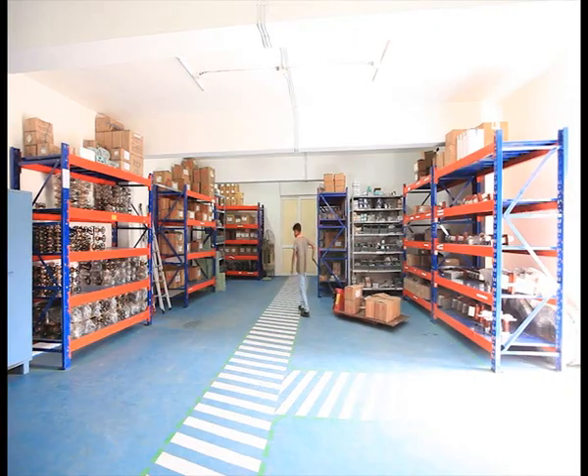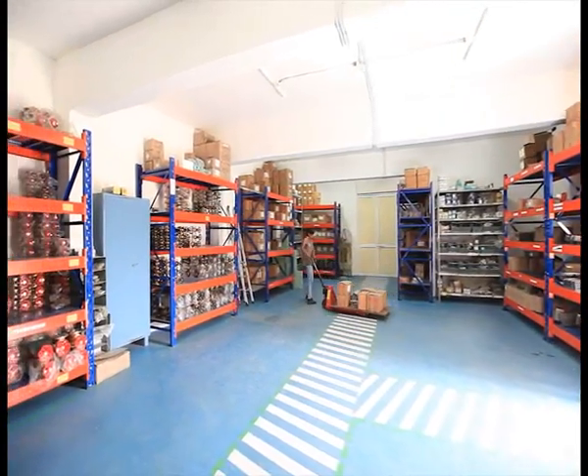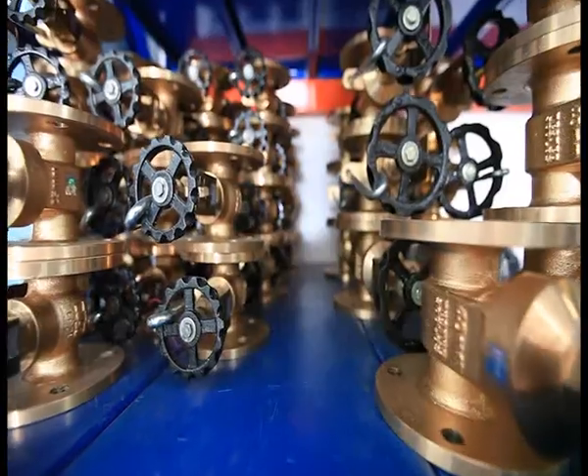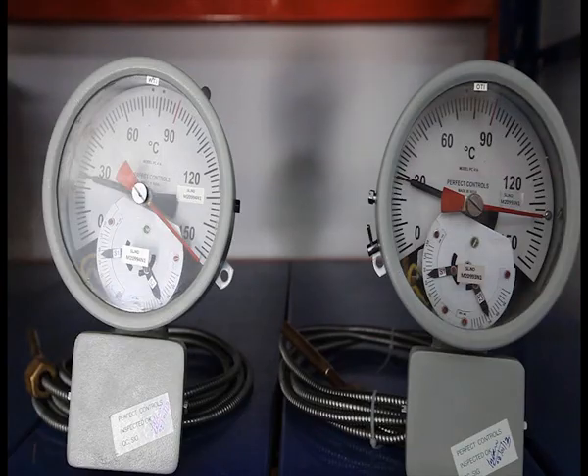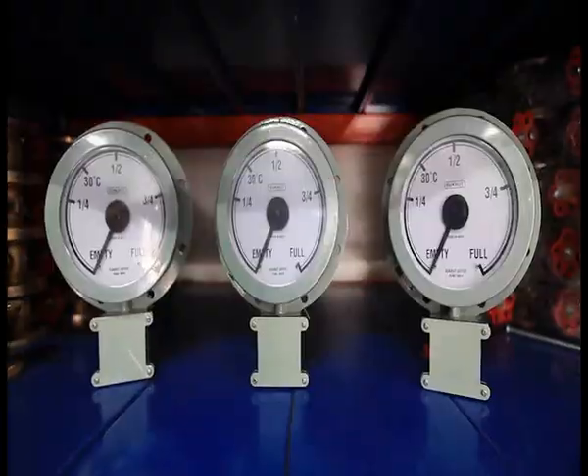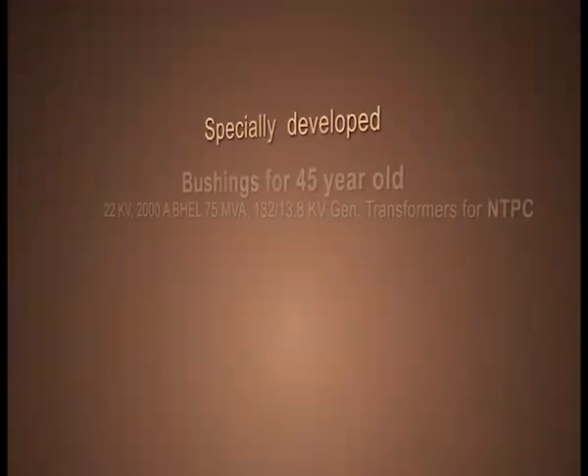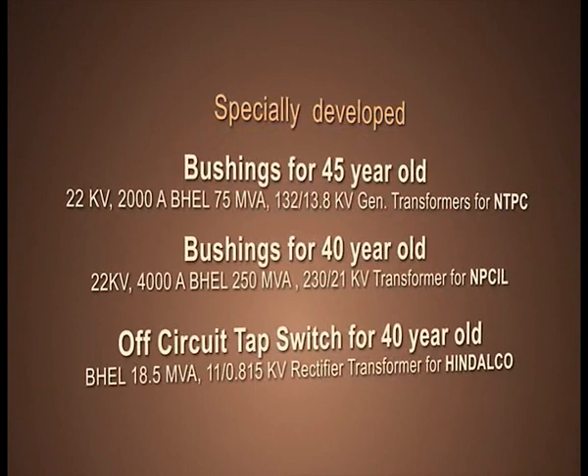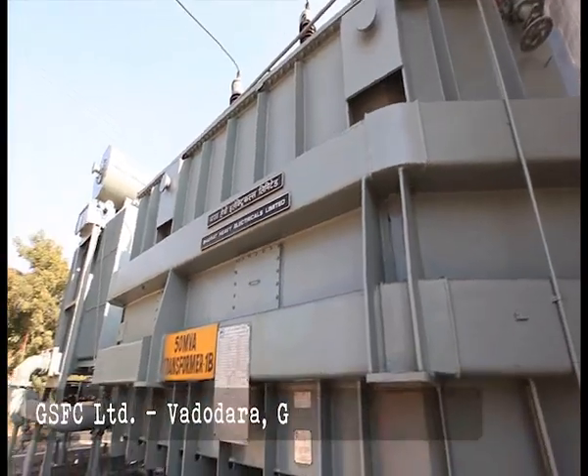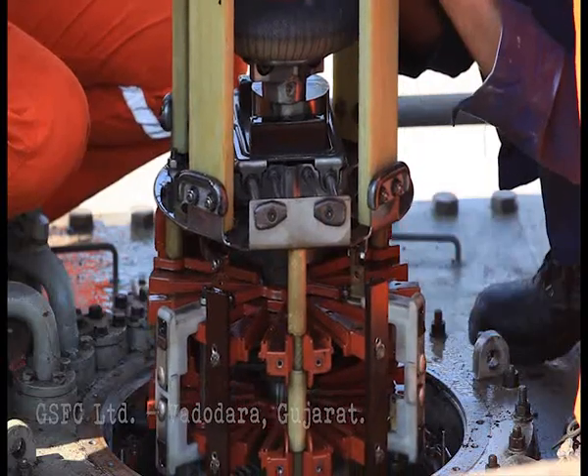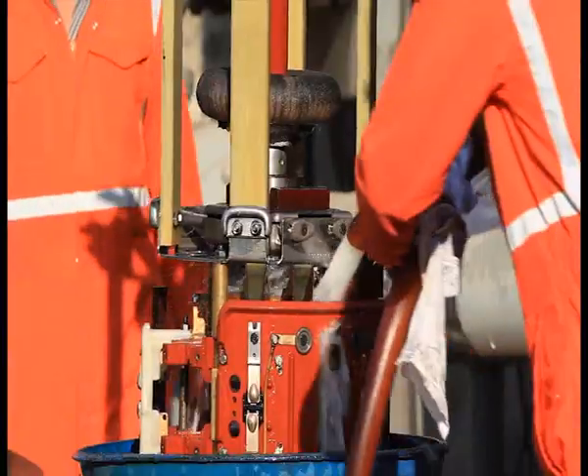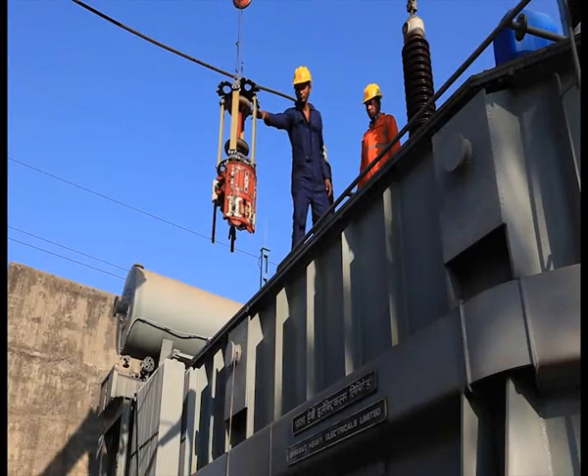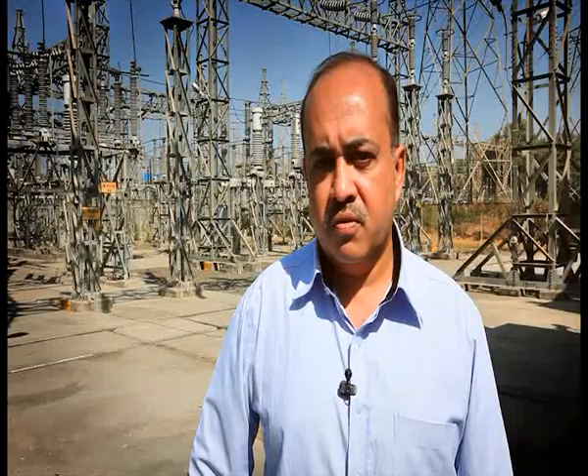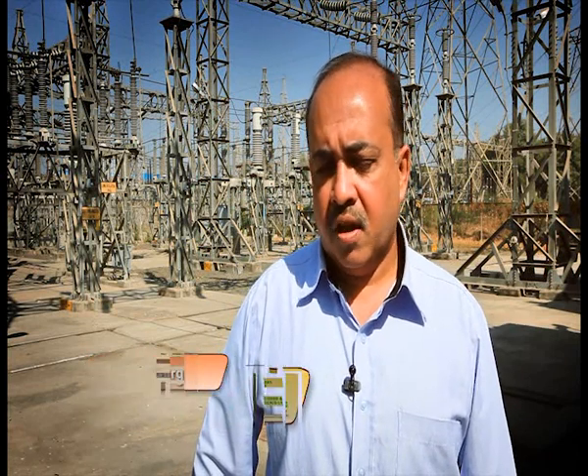Our service centers maintain adequate inventory of high-quality transformer spares. Parts that are regularly required like bushings, breathers, oil and winding temperature indicators, Buchholz relays and oil level gauges. We provide spares for any make and type of transformer and also develop parts for obsolete designs if samples or drawings are made available. Recently we had a problem with the 50 MVA BHEL transformers. We engaged services of Voltamp. Previously in our old switchyards we had Hitachi make transformers and Crompton and Greaves make transformers, where services of overhauling and replacement of certain components was done by Voltamp.